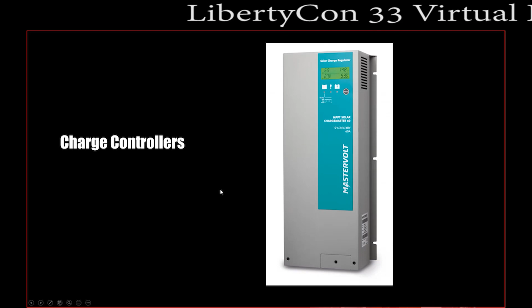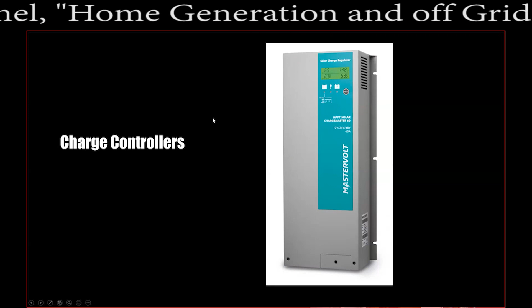You have to tune your system. If you connect an inverter directly off of your battery, the charge controller doesn't know how much power is being used. The best systems have a communications bus, so the charge controller, inverter, and battery bank are all talking to each other over a bus cable, normally a type of CAN bus arrangement, so the inverter knows how much power it has available and the charge controller knows how much the inverter is using and how much it's putting into the batteries.